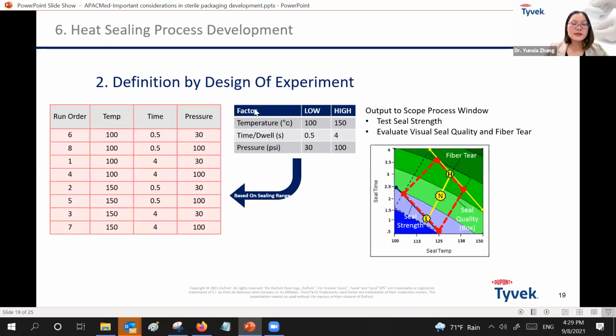And another way is this example of design of experiment. This is actually a 2-level 3-factor DOE. As we can see, the 3 factors are temperature, time, and pressure, and the 2 outputs are the seal strength and the fiber tear or visual seal quality performance. So as you can see, those contours are seal strength, and this line is the acceptable fiber tear or visual seal quality performance area. With the overlap of the two, you will be able to define this red window, and the nominal, low and high parameters will be defined in this way.